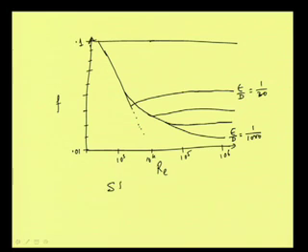These curves are popularly known as Stanton's curves, and they can be used once we know the Reynolds number and the roughness of the pipe, then we can have the value of this friction factor. Say for that Reynolds number, we will come to this curve and see what the friction factor is based on this particular roughness. Then again, another point is what this epsilon value will be.